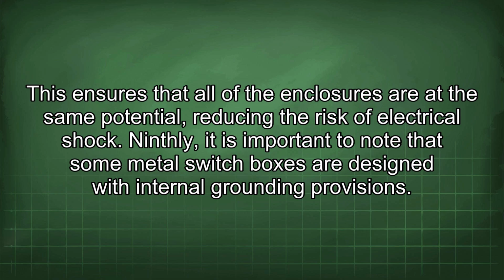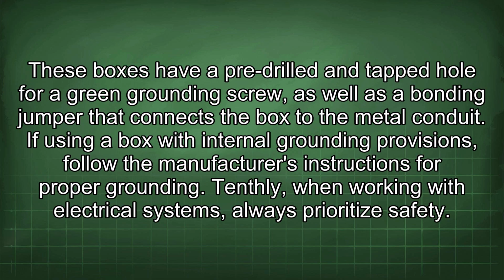Ninthly, it is important to note that some metal switch boxes are designed with internal grounding provisions. These boxes have a pre-drilled and tapped hole for a green grounding screw, as well as a bonding jumper that connects the box to the metal conduit. If using a box with internal grounding provisions, follow the manufacturer's instructions for proper grounding.